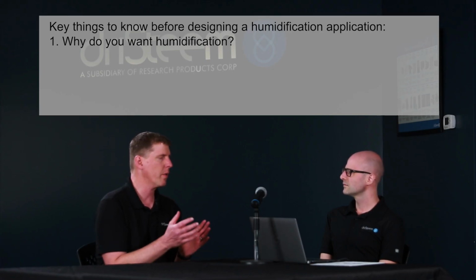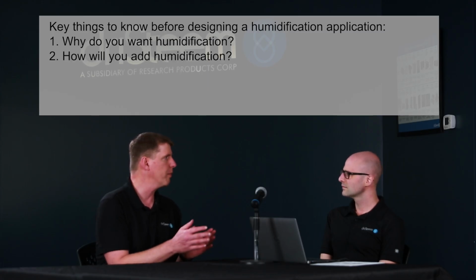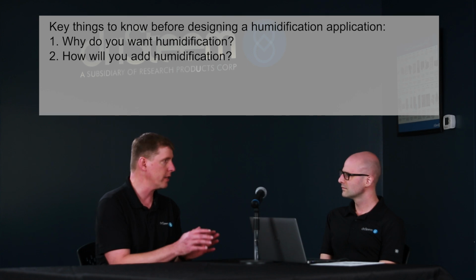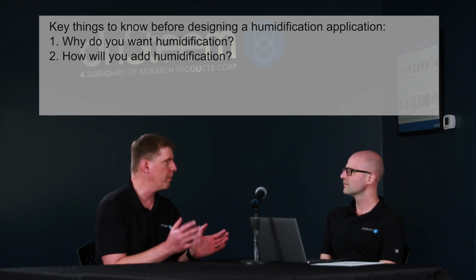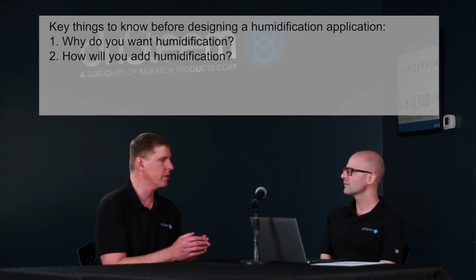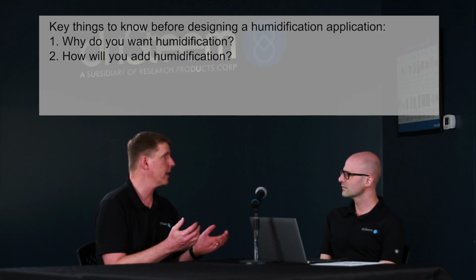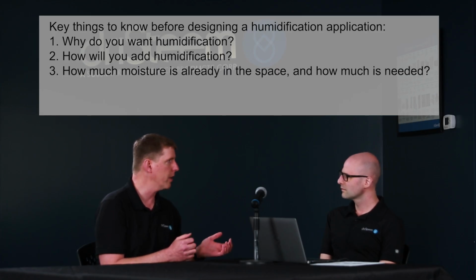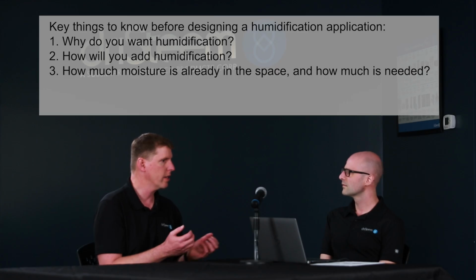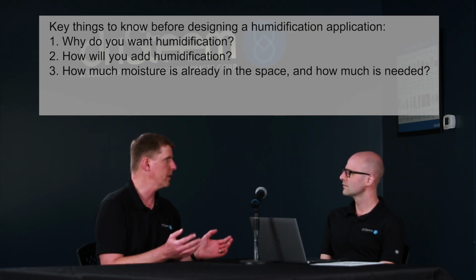Once you understand what your goals are, then it's starting to think through, okay, how do I add the moisture? I know I want the moisture because I've defined that based on the process. And it's getting into, okay, where can I put this? Am I going to go into an airstream, think of it in ductwork or in an air handler, or am I going to put it directly in the space? Then it's, okay, what is my moisture that I'm starting with and where am I ending at? Then I can know how much moisture I need to add. We've got to figure that part out before we can even get into equipment.